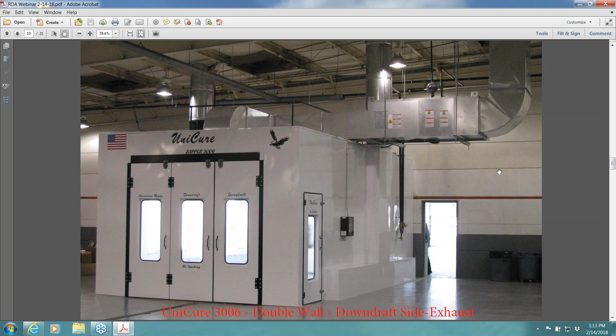There are lots of products on the market where the air makeup system is ground supported, placed on the floor. You want to make sure when talking to your customer, it's not only the working dimensions of the product - length, width, and height of the spray area - but the mechanicals adjacent to that. If you have a mechanical system that sits on the floor, that's going to take up 1.5 to 2 bays, versus a mechanical system that can be placed in the air. This is what we typically try to do, but as you'll see in the next picture, it's not always the case - this is that same air makeup system, suspended from the ceiling with threaded rod, which is something you have to pay attention to - what is the ceiling made out of?